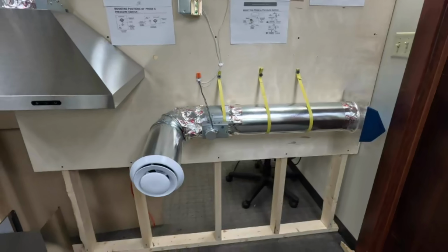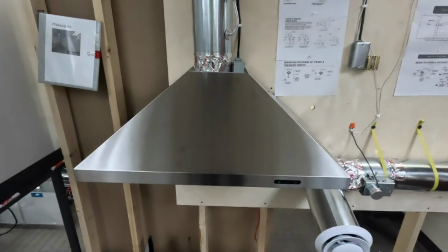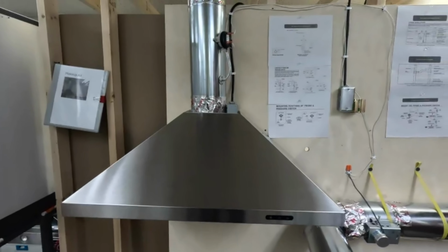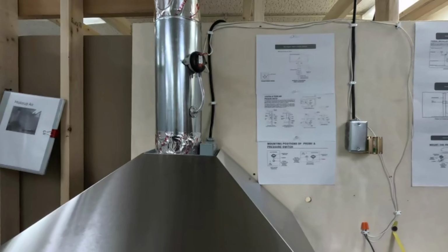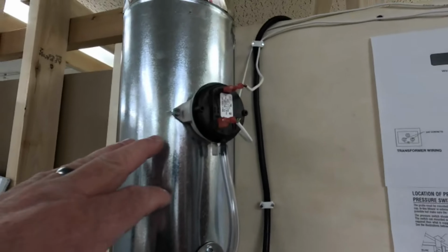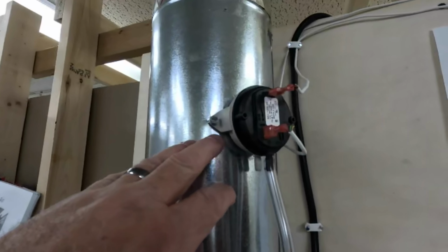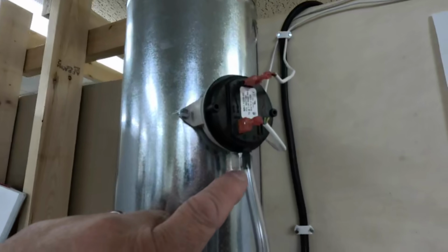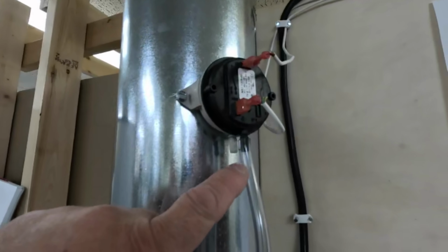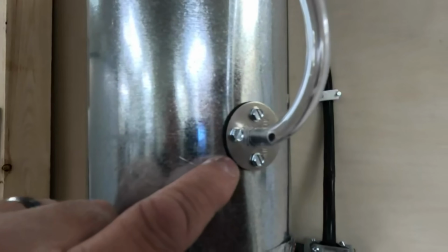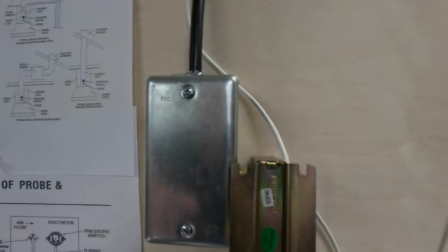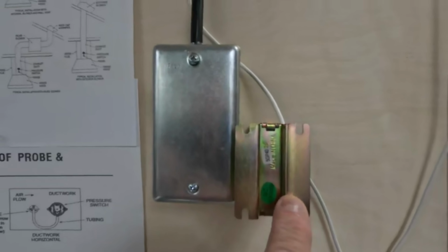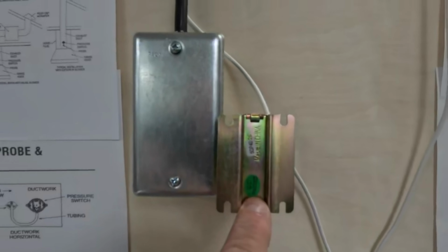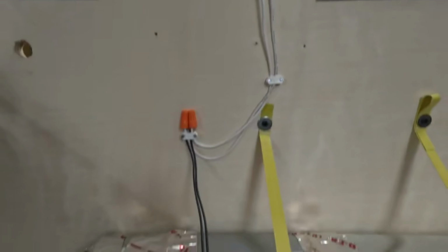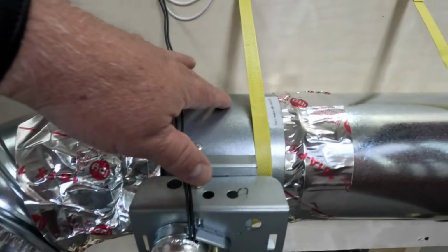If you take a look, the makeup air system consists of a couple of things. One, the main switching device is a pressure switch. It comes with a tube, and it also comes with a probe. This probe sticks inside this ducting. It also comes with a transformer, and this transformer basically sends 24 volts to the makeup air damper, and this is the makeup air damper.